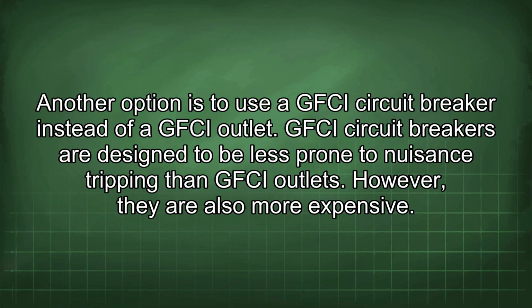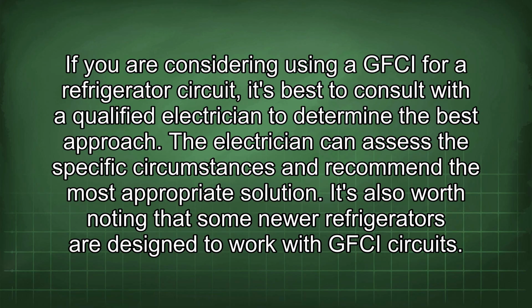Another option is to use a GFCI circuit breaker instead of a GFCI outlet. GFCI circuit breakers are designed to be less prone to nuisance tripping than GFCI outlets. However, they are also more expensive. If you are considering using a GFCI for a refrigerator circuit, it's best to consult with a qualified electrician to determine the best approach. The electrician can assess the specific circumstances and recommend the most appropriate solution.